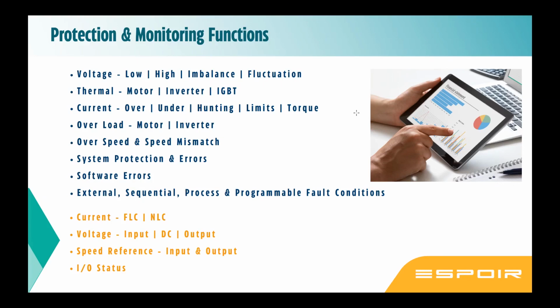Then current. Overcurrent, it trips. Undercurrent, it can trip. If current is hunting, it can trip. Limits, you can set a higher limit and a lower limit of a current. You can also do a torque setting. Beyond a certain torque or below a certain torque, the system should trip. It can do that. Again, we need to program, define, select a model.